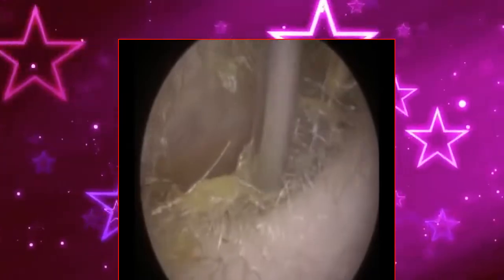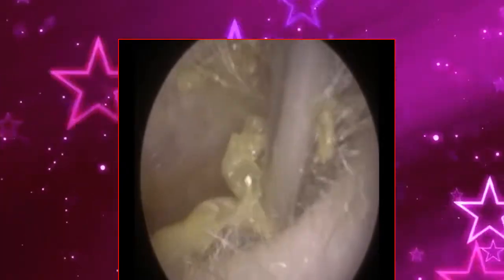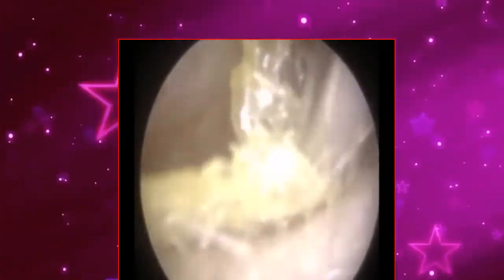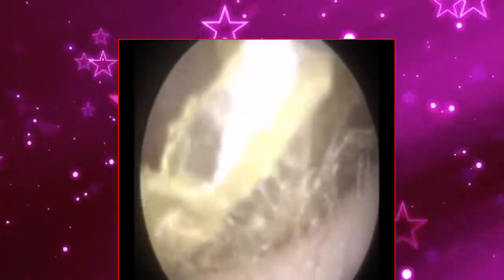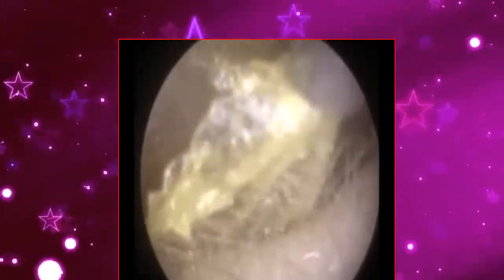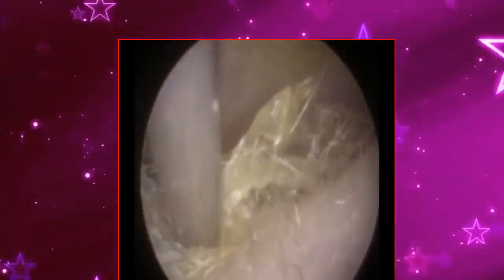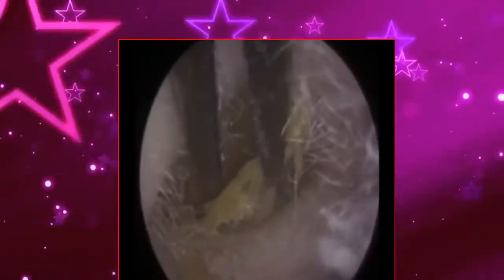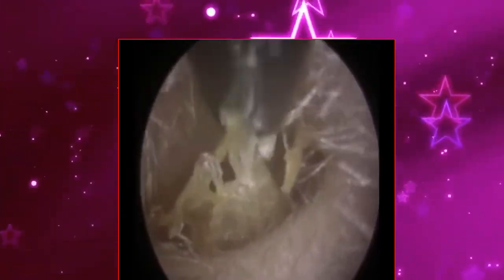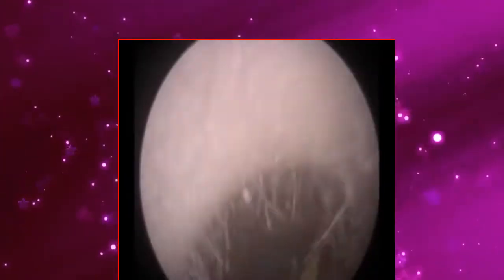What I've done here is attach a fine end gauge onto the suction probe, and the reason for that is that this remaining bit of debris in the ear is not actually earwax, it's keratin, so dead skin. The problem with keratin is that when you suction keratin, you can get clarinetting, which is a very loud, audible, high-frequency squeal, and it's almost deafening. What I find is that when you attach a fine end gauge, it reduces that clarinetting, so it's more comfortable for the patient. However, even with the fine end, it wasn't really removing that keratin, so I resorted to some crocodile forceps to gently peel that keratin off the canal wall.